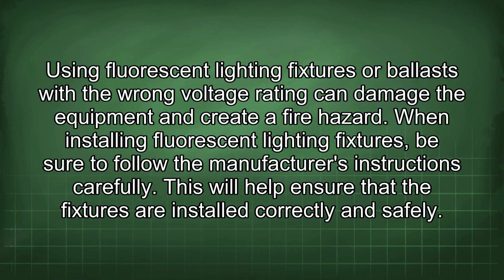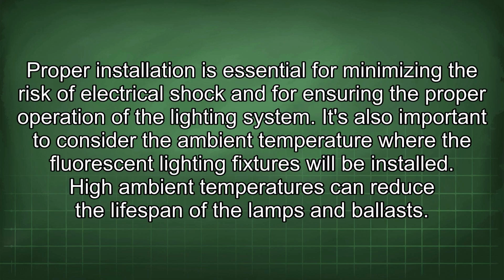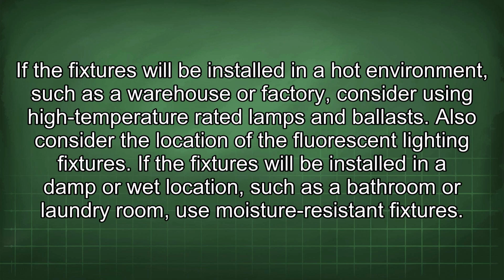When installing fluorescent lighting fixtures, be sure to follow the manufacturer's instructions carefully. This will help ensure that the fixtures are installed correctly and safely. Proper installation is essential for minimizing the risk of electrical shock and for ensuring the proper operation of the lighting system. It's also important to consider the ambient temperature where the fluorescent lighting fixtures will be installed. High ambient temperatures can reduce the lifespan of the lamps and ballasts. If the fixtures will be installed in a hot environment, such as a warehouse or factory, consider using high temperature rated lamps and ballasts.